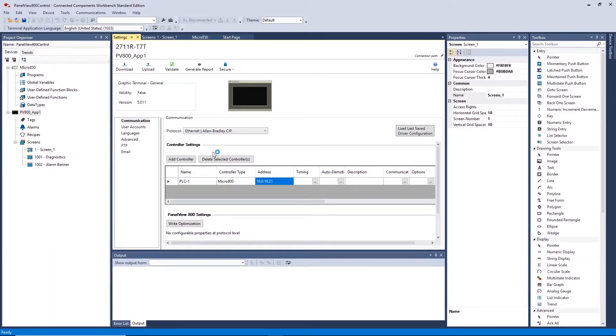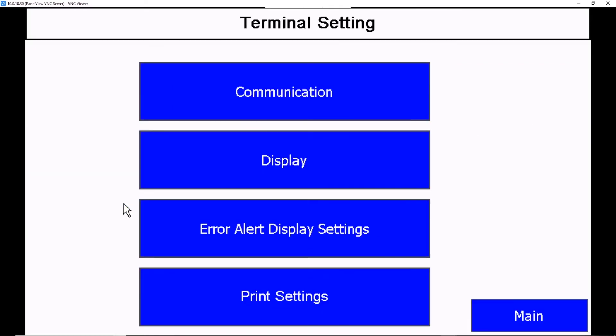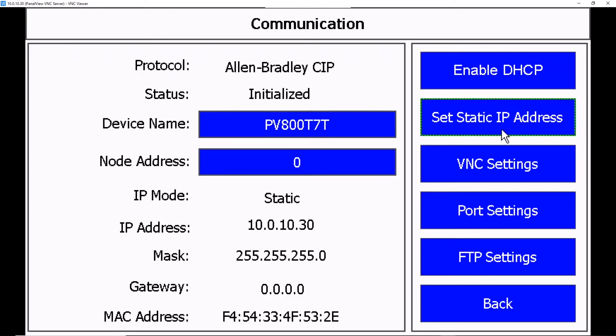To communicate with the PLC we need our HMI set to a unique IP address on the same subnet as the controller. This is done on the HMI. Click Terminal Settings, Communication, Set Static IP Addresses, Click on IP Address or Subnet Mask to change.